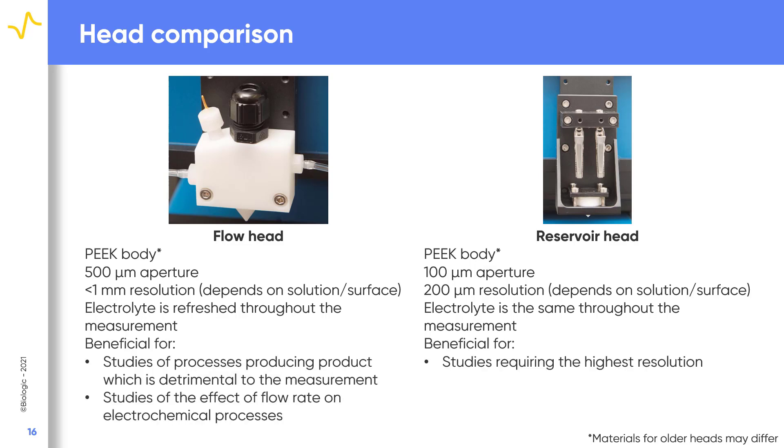The SDC flow head is a good choice for studies of processes producing products detrimental to the measurement of interest, as well as studies where the effect of flow rate on the electrochemical process is of interest. The SDC reservoir head is of interest when the highest resolution SDC measurements are needed.